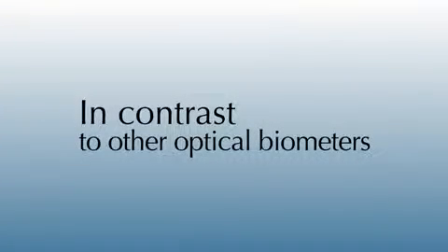I was very impressed with the reproducibility of LENSTAR Ks, probably some of the best I've ever seen. Up until now, we've been using the IOL Master 2.5 millimeter zone Ks, or software version 5.4, and that's been sort of our go-to measurement technique. I think the LENSTAR Ks are actually better, and we're very, very confident with them.